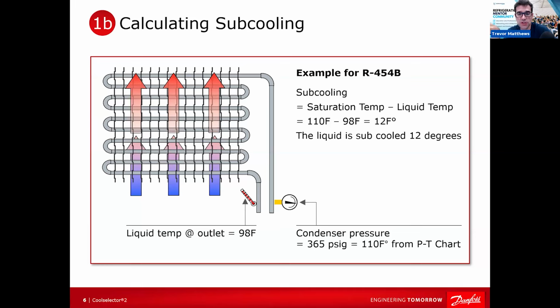And then sometimes you can't check it at the condenser perfectly, right? So sometimes you've got to get the pressure from a different place. But getting the temperature at the outlet, checking your subcooling at the outlet of the condenser, and I meant at the inlet of the TX valve. You want to know what the temperature at your TX valve is as well in the system. So checking your subcooling there is important as well. But a lot of times you don't have the pressure port at the inlet.